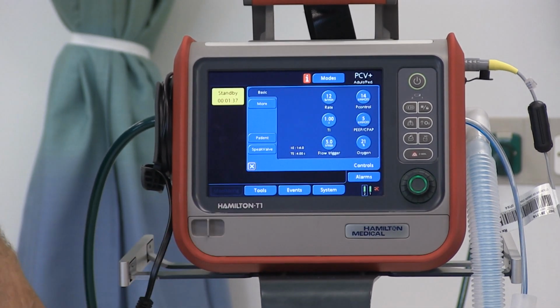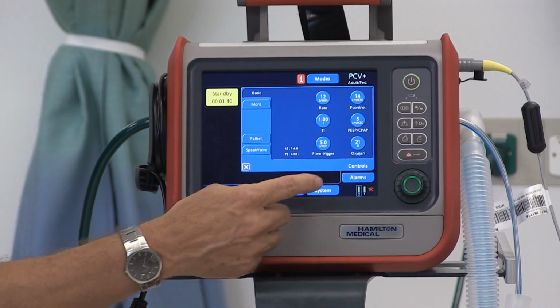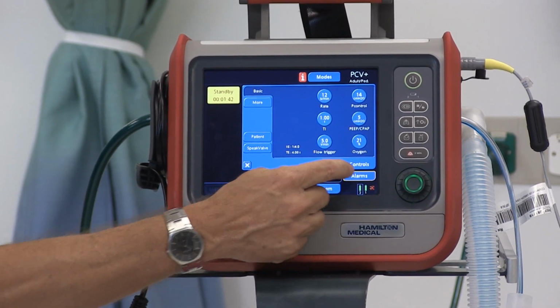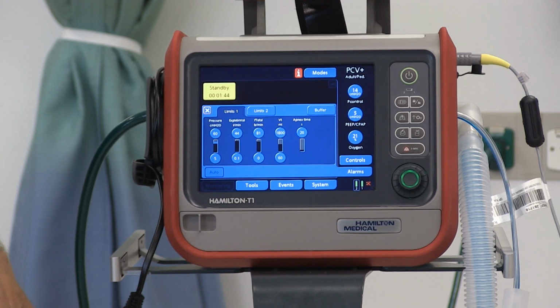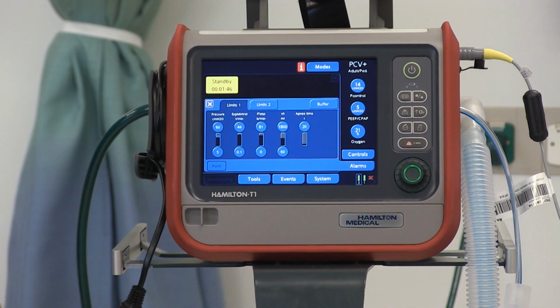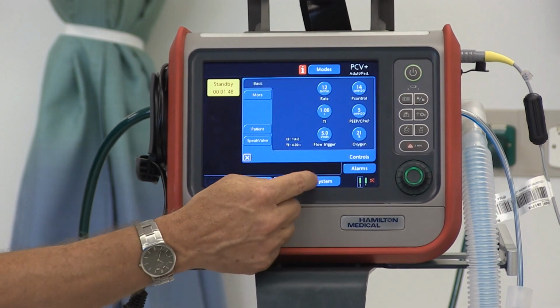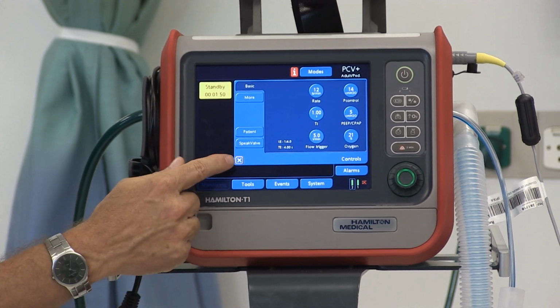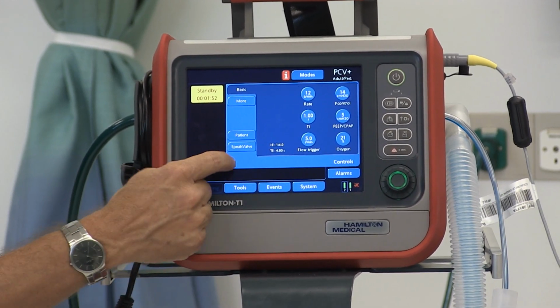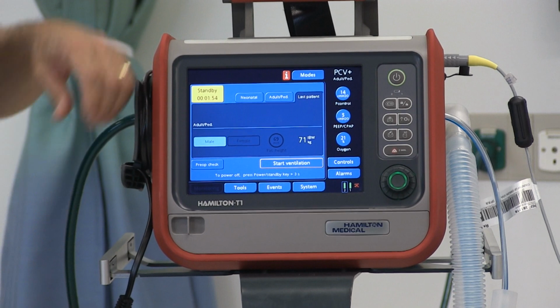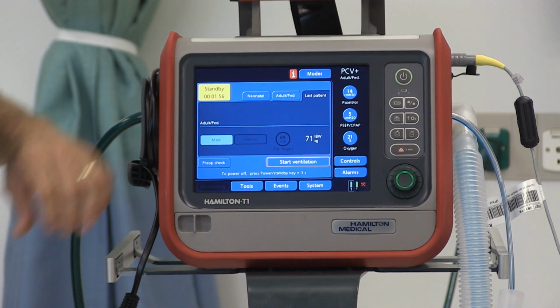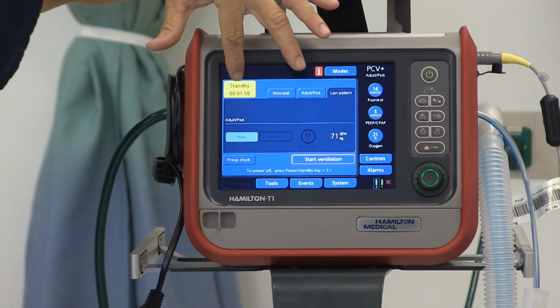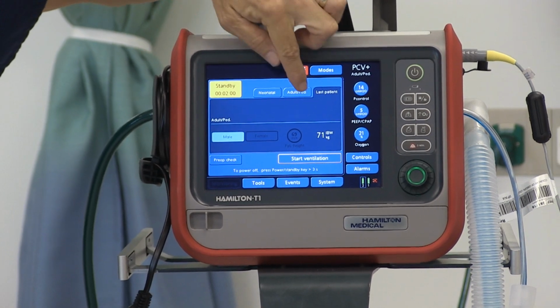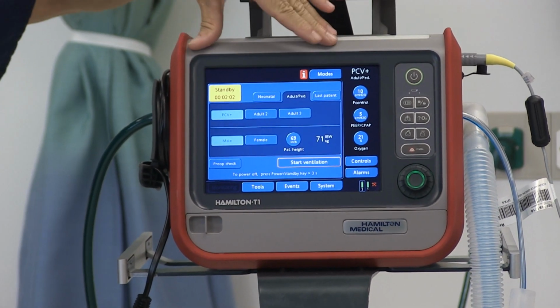To open the controls, I press the controls tab. To open a different window, I press, for example, the alarms tab, and it opens a different window. So to navigate between windows, I just hit different tabs, or to close a tab, I can touch the X in the lower left corner. Here on the main part of the screen, you can see that we are in standby. There's the standby timer right there. And for a new patient, the screen looks like this.